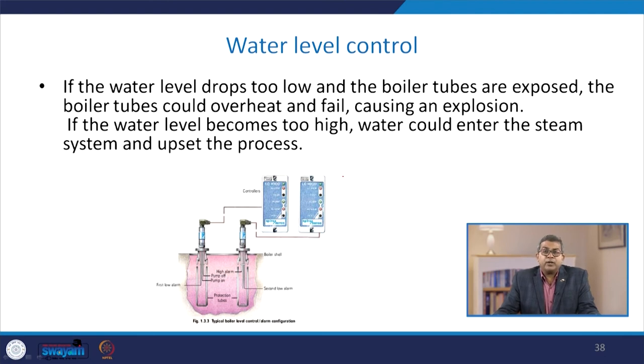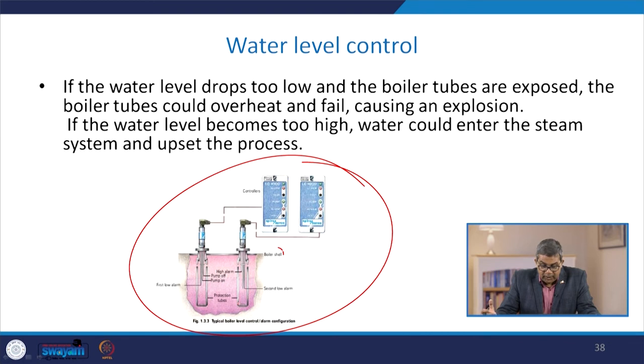The water level controller discussed in the previous section: this is the typical boiler level control and alarm configuration, always coupled with an alarm. It is fitted with the boiler shell with protection tubes, since the quality of steam and safety of the boiler always depends on accurate water level. If the level is too low, tubes could overheat and may cause explosion; if too high, carryover may take place.